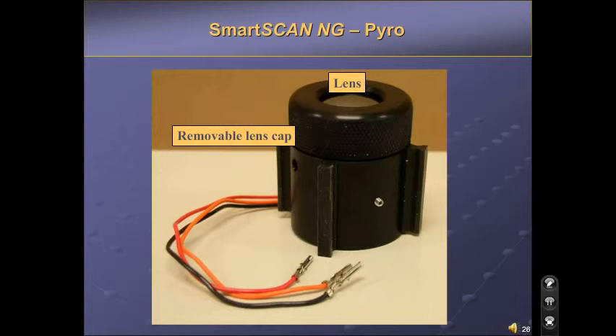The Pyro assembly has a removable lens cap. If the lens should become extremely scratched or deteriorated, a new lens can be installed. If you install a new lens, it will be necessary to recalibrate the scanner.